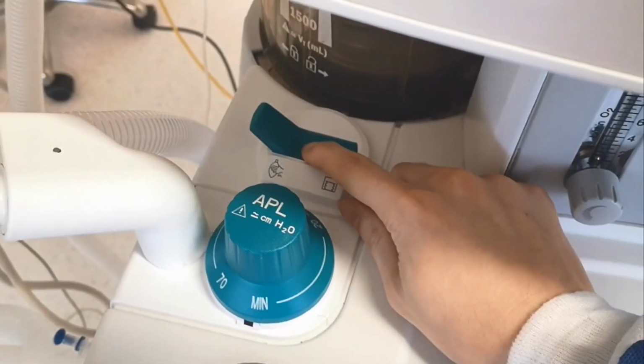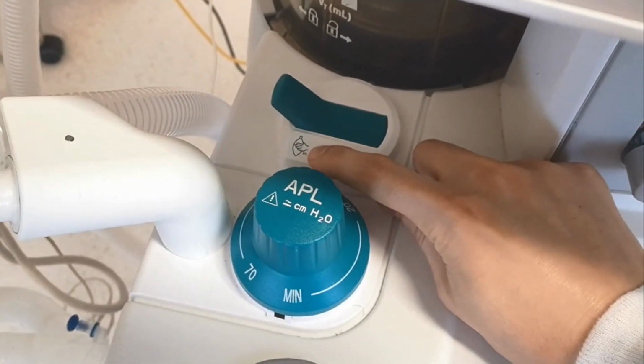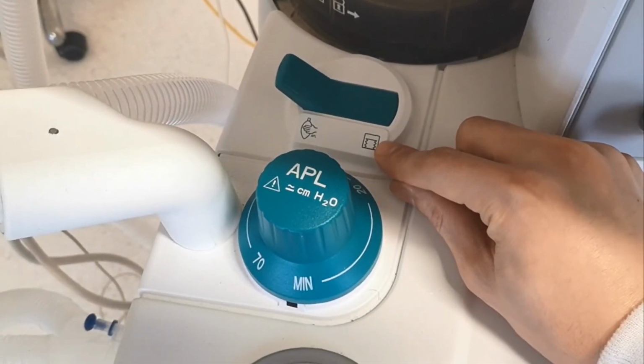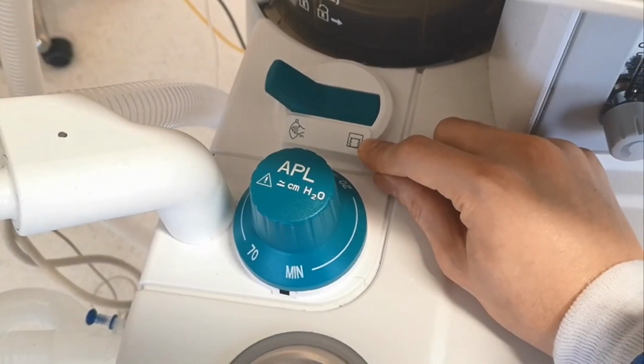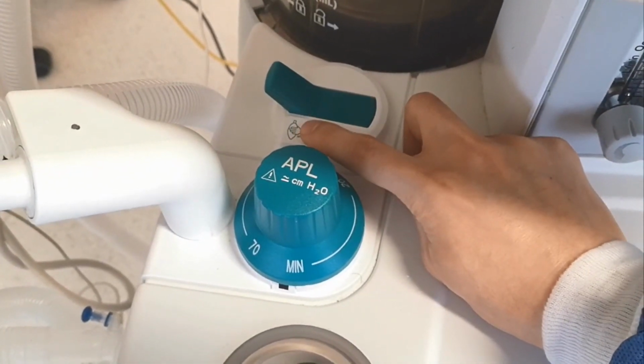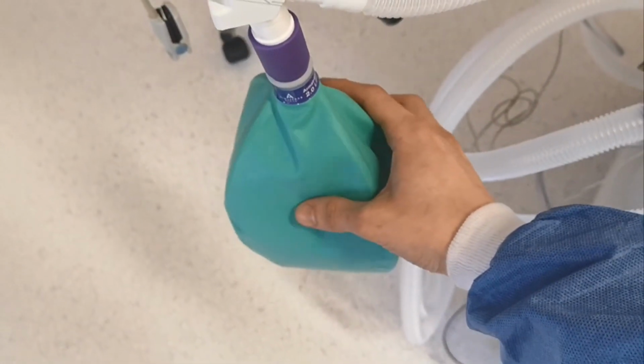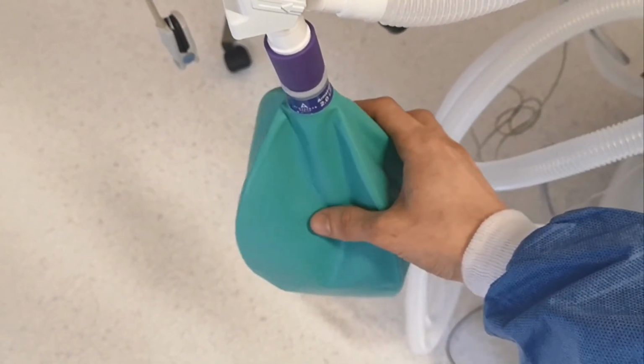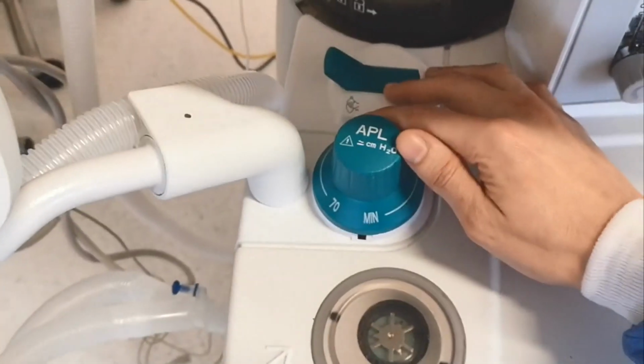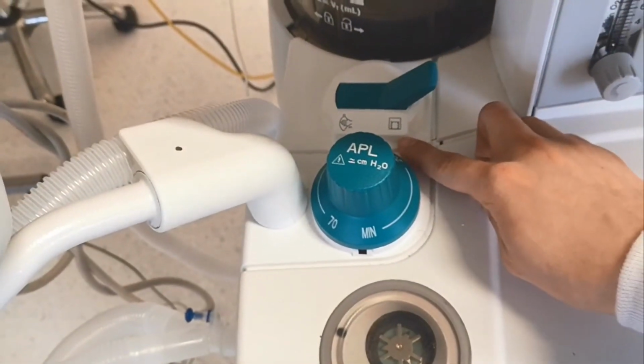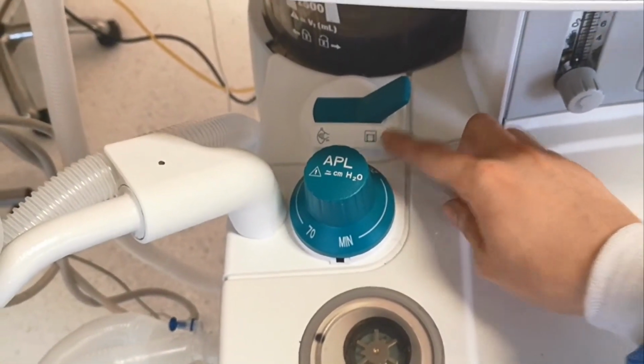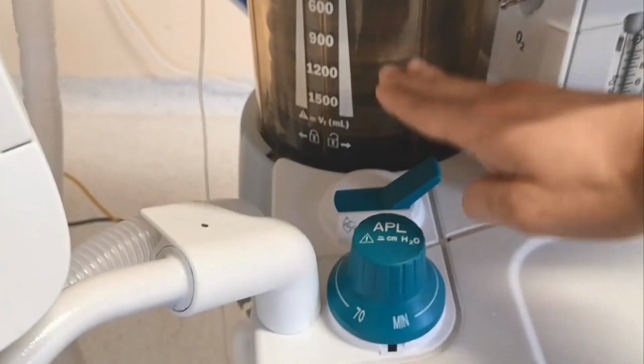Now, as you see here, there is a switch. There's a little sign of a bag and a symbol of a ventilator here. Now, these machines allow you to bag the patient manually. So you turn this to the bag, and then you can use the bag that is here to pump air into the patient's lungs. Or you can control switching this to the ventilator symbol, and then the machine pumps air in and out.